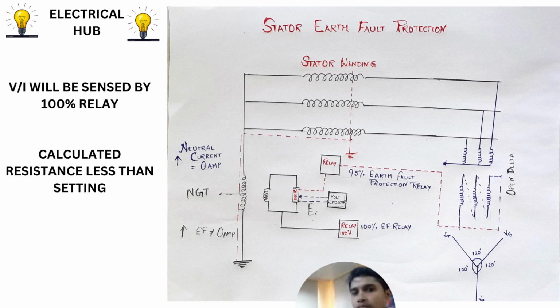Now try to understand one thing: when a voltage is injected and a fault occurs, then the resistive current will also flow through the NGT, and that current will be sensed in the secondary of the NGT. So voltage is there, current is there, so V by I is equal to R. That resistance will be sensed by the protection relay to protect the 5% of the winding.